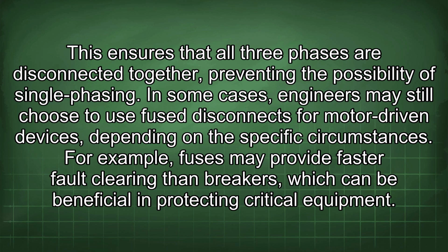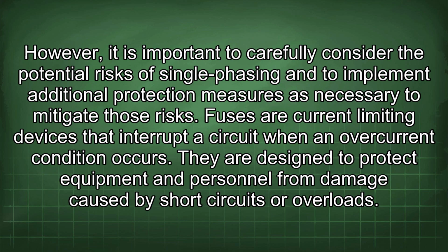In some cases, engineers may still choose to use fused disconnects for motor-driven devices depending on the specific circumstances. For example, fuses may provide faster fault clearing than breakers, which can be beneficial in protecting critical equipment. However, it is important to carefully consider the potential risks of single phasing and to implement additional protection measures as necessary to mitigate those risks.